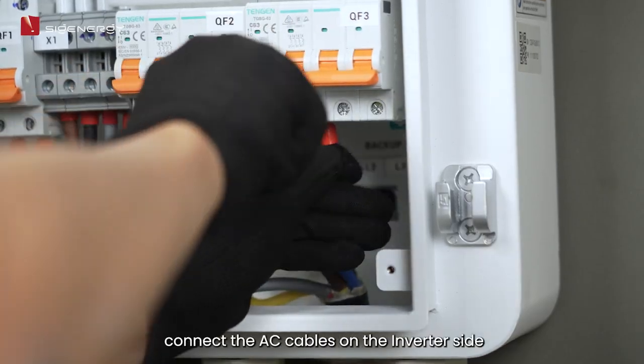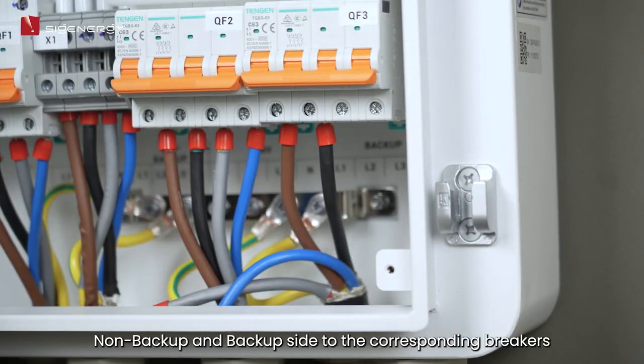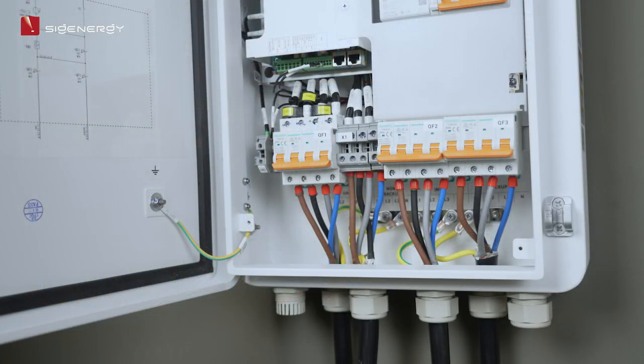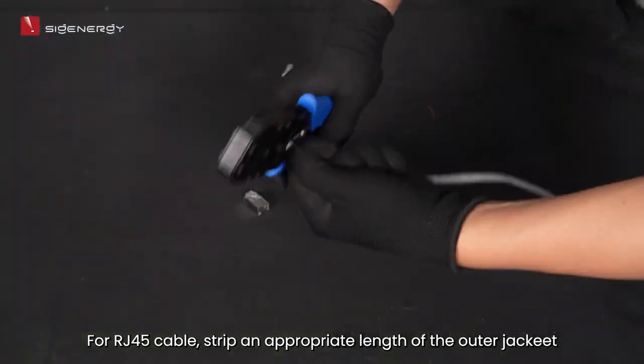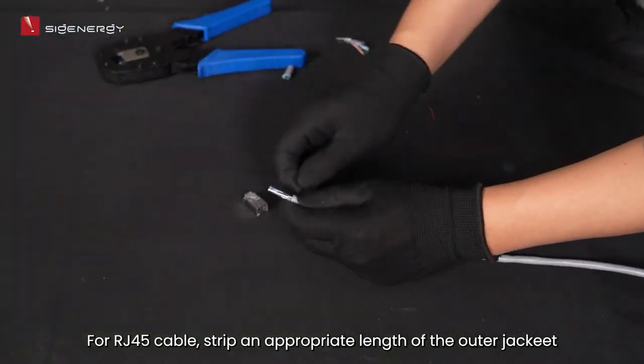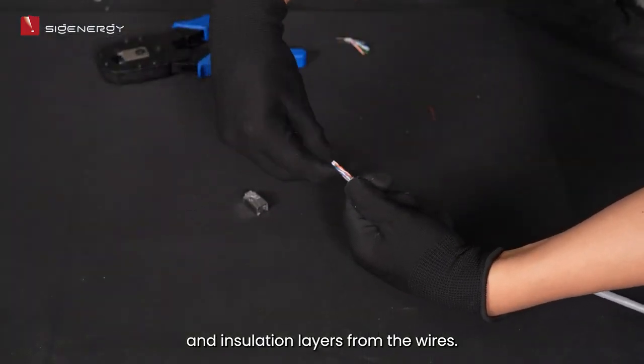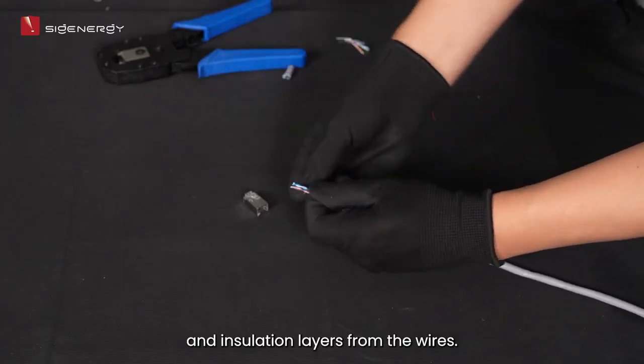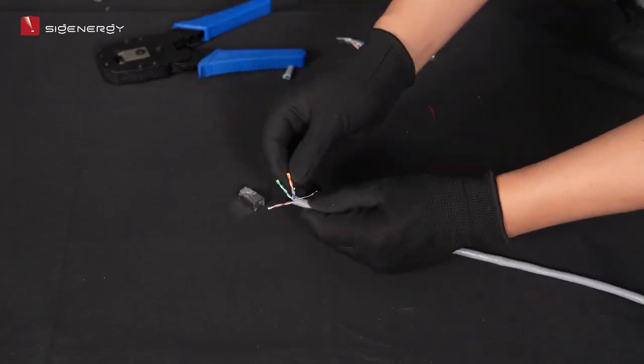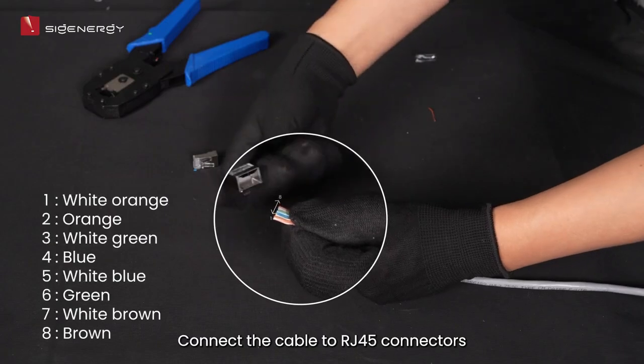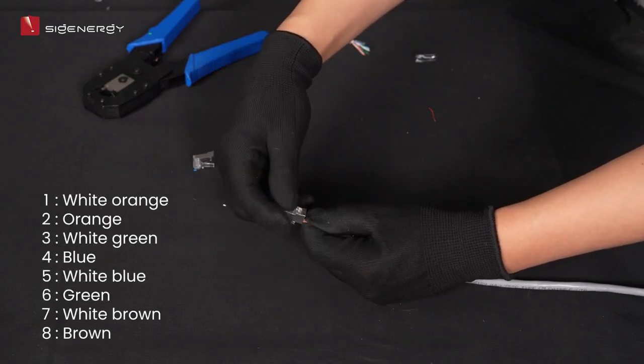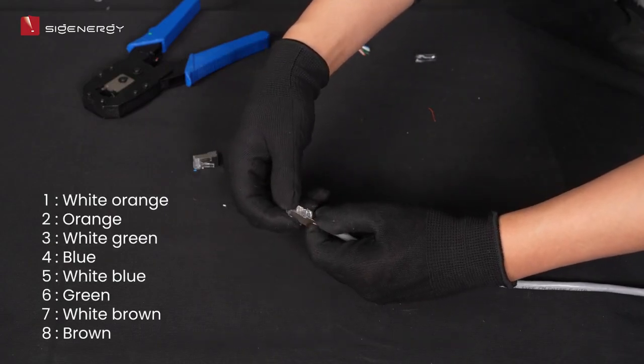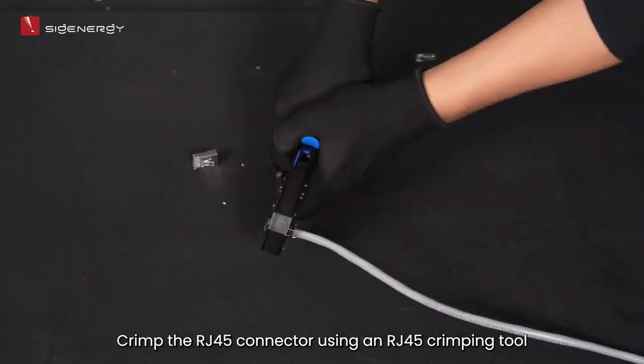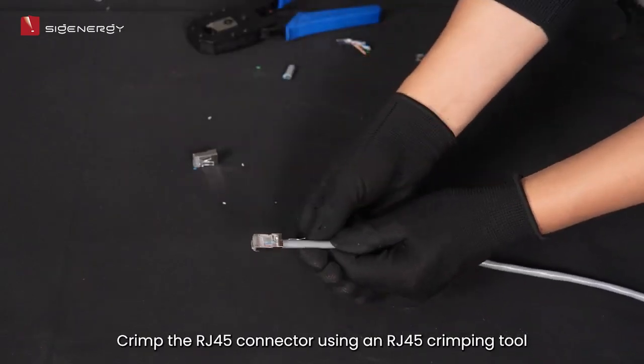Similarly, connect the AC cables on the inverter side, non-backup and backup side to the corresponding breakers. For the RJ45 cable, strip an appropriate length of the outer jacket and insulation layers from the wires. Connect the cable to RJ45 connectors. Crimp the RJ45 connector using an RJ45 crimping tool.